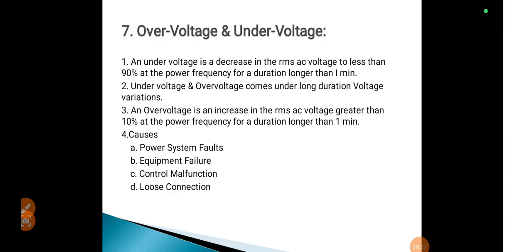The next is over voltage and under voltage. Under voltage is a decrease in RMS AC voltage to less than 90% at the power frequency for a duration longer than 1 minute. Under voltage and over voltage come under long duration voltage variation. The causes of under voltage and over voltage are power system faults, equipment failures, control malfunction, or loose connections.